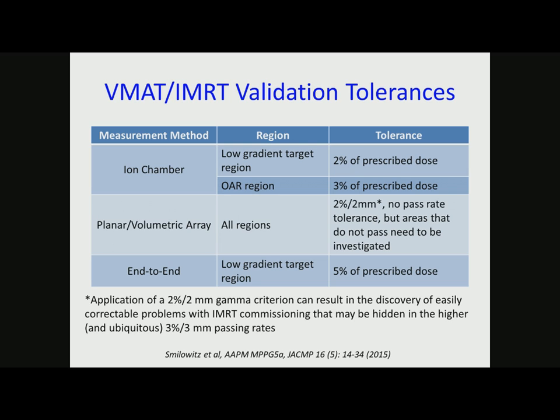So here there's a nice table in this document telling you about some tolerances. For the PTV area, for example, if you're doing an ion chamber, it's about 2% of prescribed dose. That's a low gradient area, it's more homogeneous. And the organs at risk region, where there's some gradient, 3%. If you're doing some kind of planar dosimetry for QA, for example IMRT, VMAT QA, or ArcCheck for a volumetric array, they suggested 2%, 2 millimeter, not 3%, 3 millimeter like most people use.